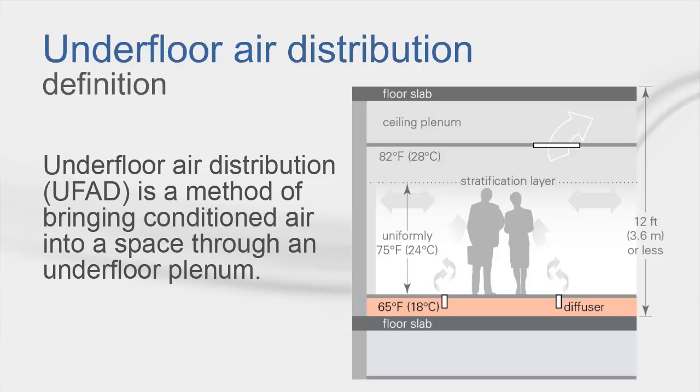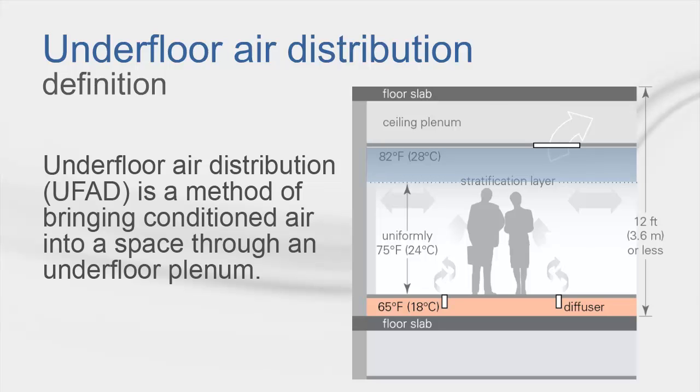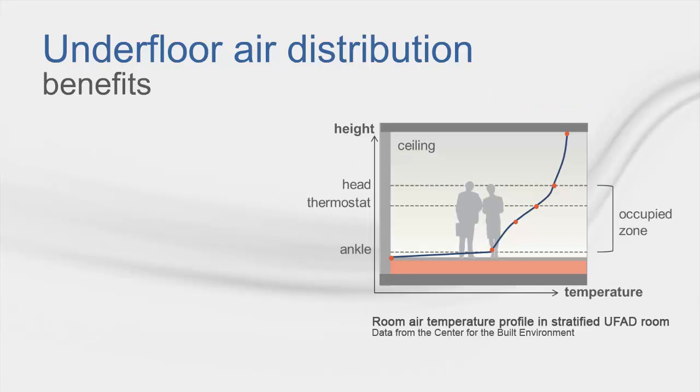Let's begin with discussing what is underfloor air distribution. UFAD systems typically deliver conditioned air to the space through diffusers mounted in the raised floor. You can see in the diagram on the right that this swirling supply air mixes with air from within the space, creating a mixed air region in the lower portion of the space. Then, temperature stratification occurs in the upper portion of the space.